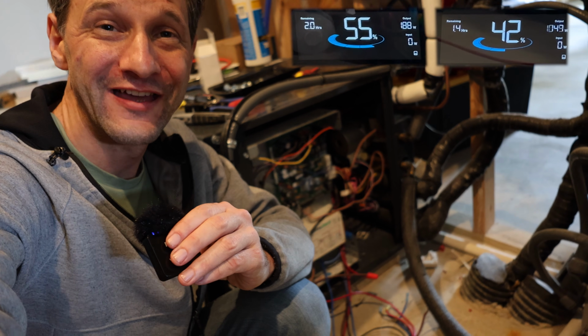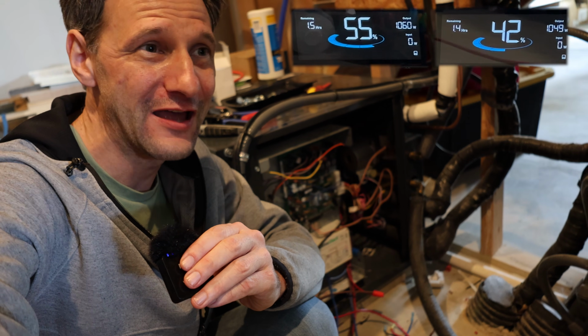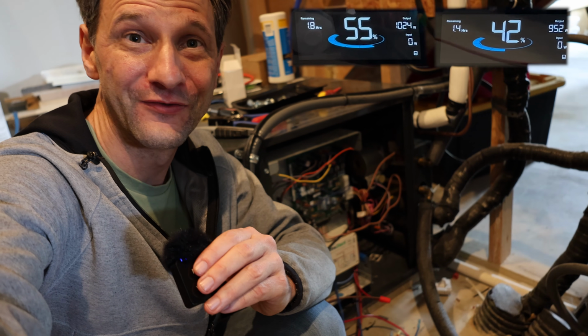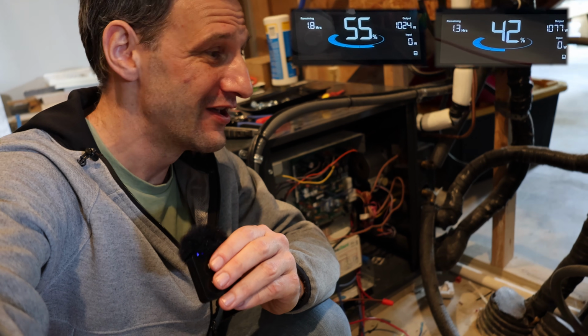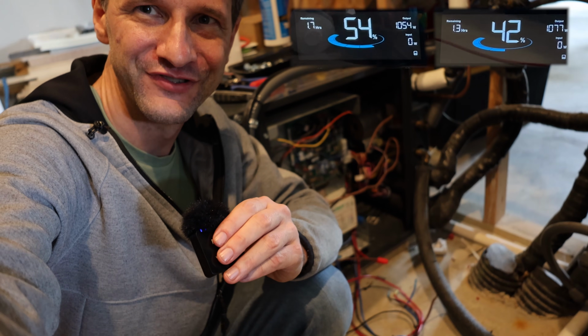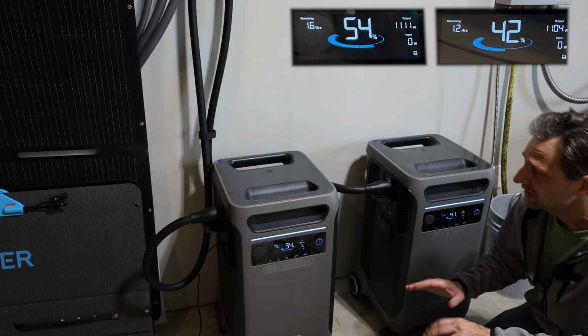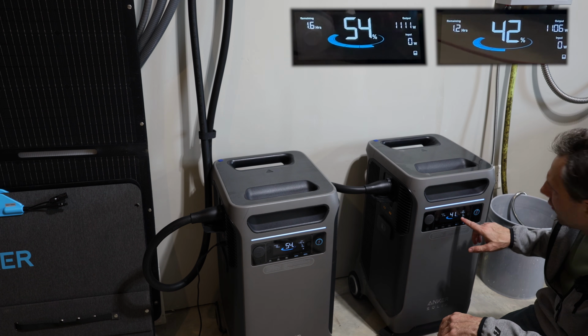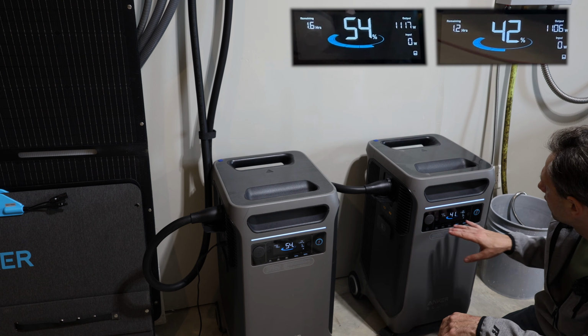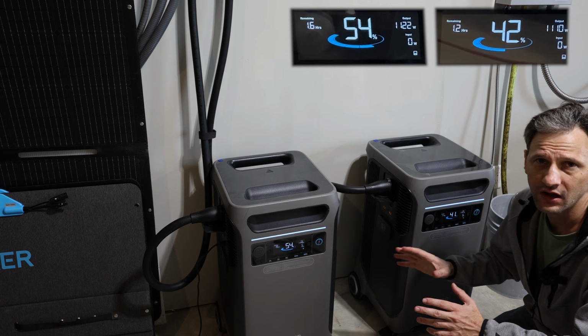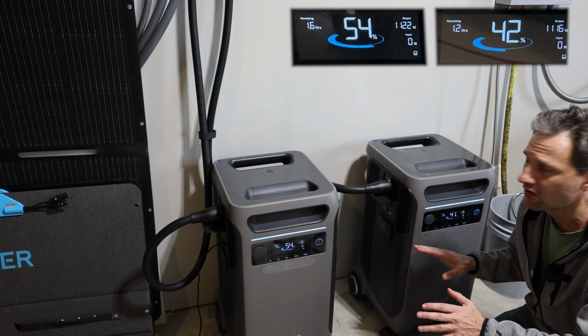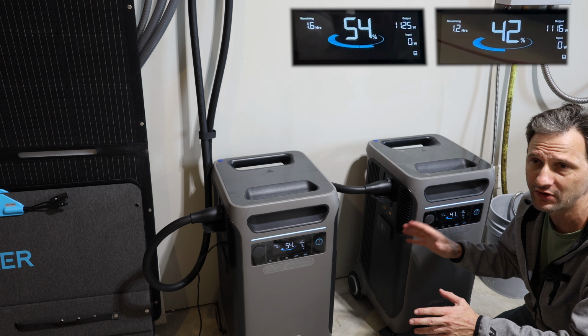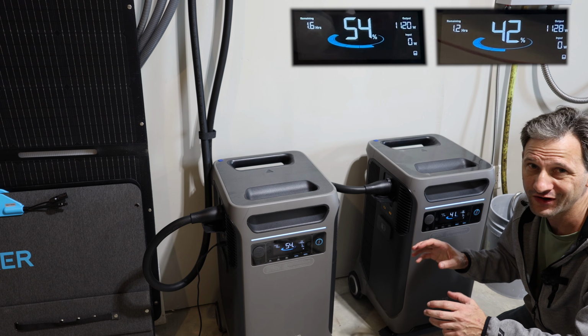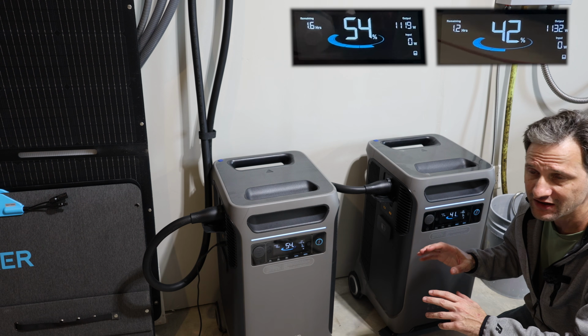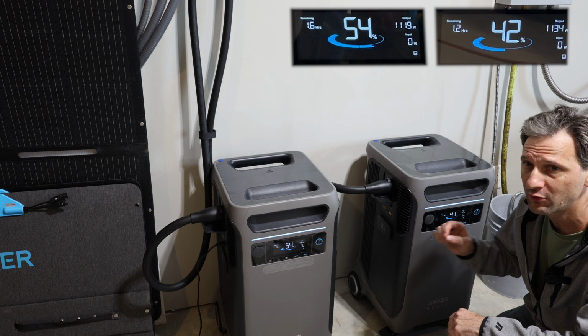How about that? That is the smoothest startup I've ever had with one of these transformerless inverters. That is awesome. 4-ton heat pump test? Check. And you can see once it starts up, we're only pulling 2,300 watts or so. It's not the running that's hard—it can run it all day, no problem. It's really not that much load. It's the starting that's an issue. And if you want to have any chance at all to get it to start, you're going to need one of those soft starters.